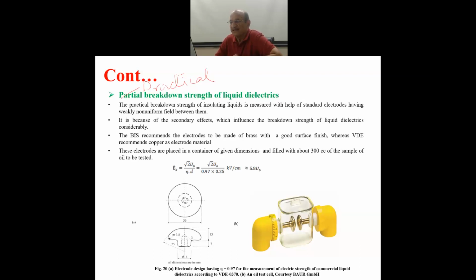The BIS, the Bureau of Indian Standards, recommends the electrodes to be made out of brass with a good surface finish, whereas VDE, the German standard, recommends copper as electrode material. The electrodes are placed in a container, as you can see on the right side, of given dimensions and filled with about 300 cc of the sample of oil for which you would measure the breakdown strength. There is a recommended procedure for increasing the applied voltage: you cannot increase it suddenly, it has to be increased gradually. It's all specified.